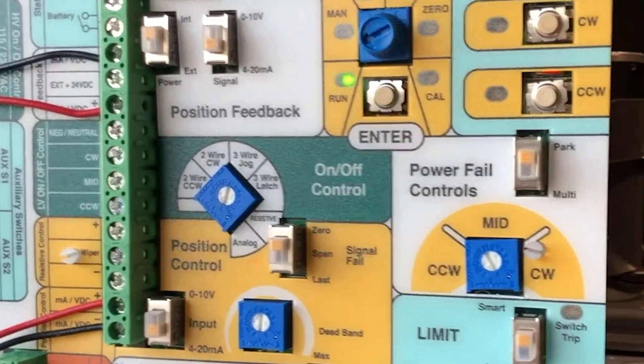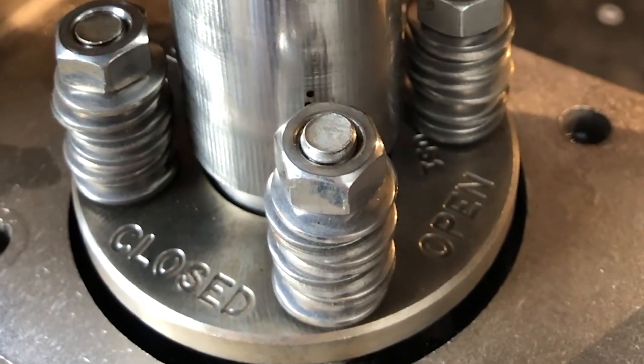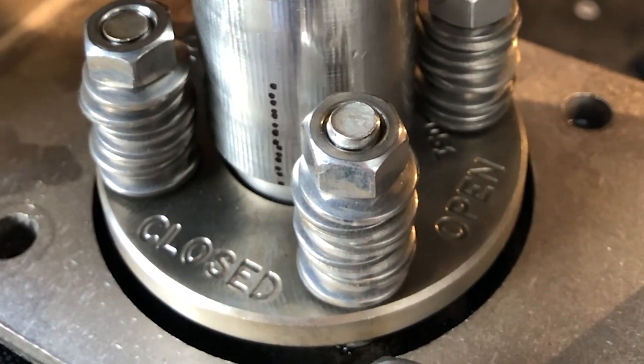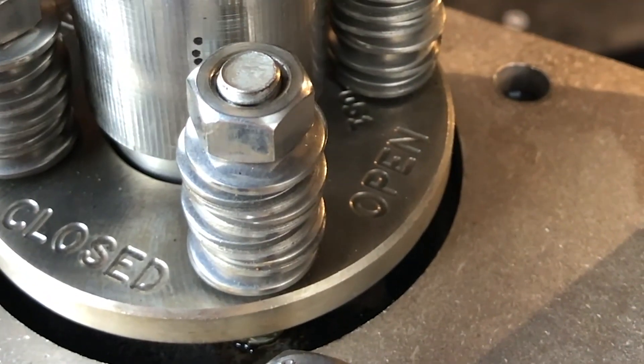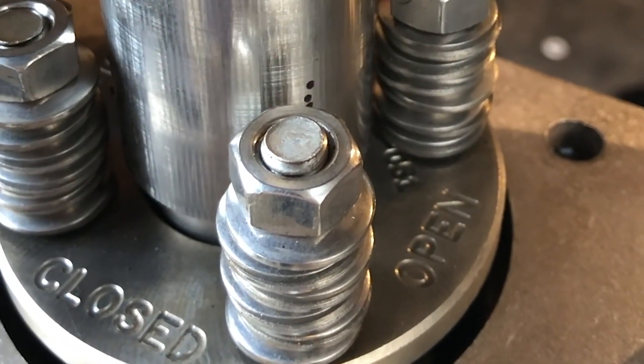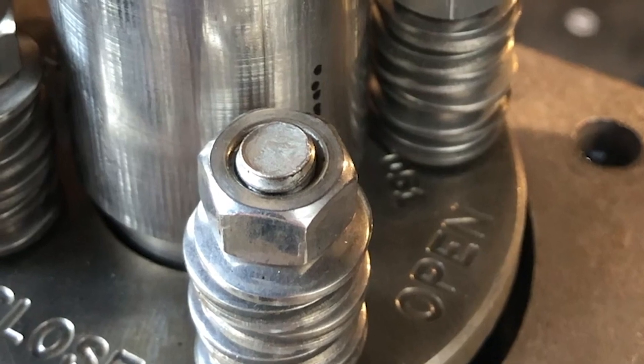The run LED is on and now we can simulate our four to 20 milliamp signal to verify that we get the correct orientation whenever we apply that milliamp signal. So right now I'm going to apply four milliamps, should be in the closed position which it did. Next I'm going to drive it back open to 20. As you can see on your valve, your valve should go to the fully open position with 20 milliamps applied.